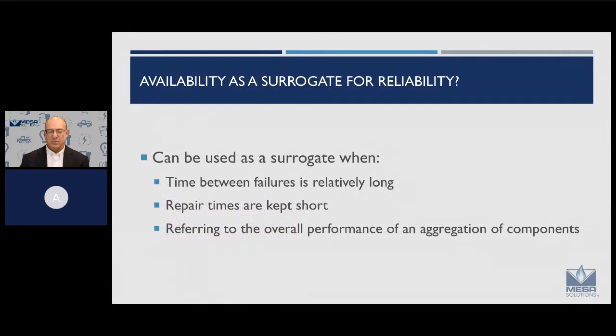In this case, we're wanting to use availability as a surrogate for reliability, and that makes a lot of sense when the time between failures is relatively long and when the repair times to the system are relatively short, especially when you're referring to an overall aggregated system.